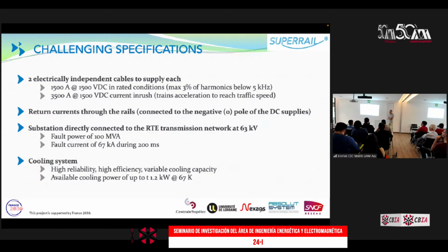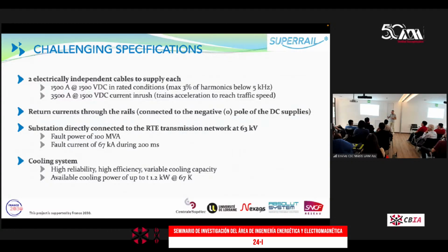What is very challenging for this cable is that it needs to sustain a short circuit of about 67 kiloamps during 200 milliseconds. And this is very challenging because during these short circuits, you need to maintain the electrical insulation. You need to maintain that the cable is still operating, at least that the temperature does not increase too high. And what is very challenging, you need to avoid heating the liquid nitrogen and making bubbles. Because if you have bubbles in the cryostat of the cable, then you lose the electrical insulation. The electrical insulation is made of 2 parts. There is some kraft paper between the conductive part and the other conductor, but it is mainly due also to the liquid nitrogen. So if you have some bubbles somewhere, you will lose the electrical insulation.